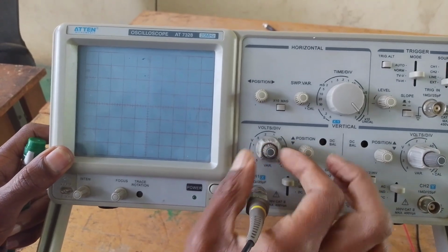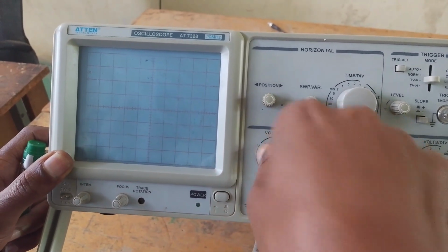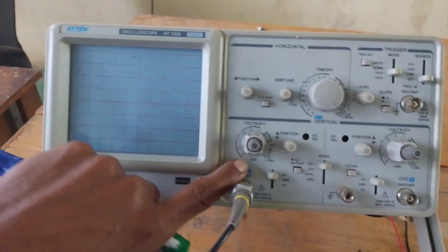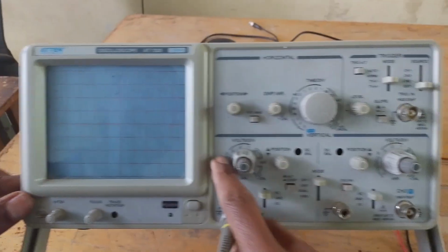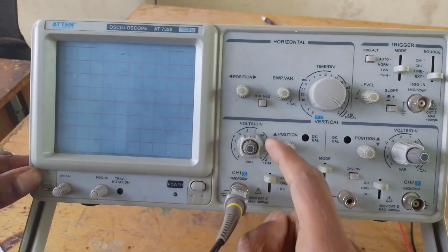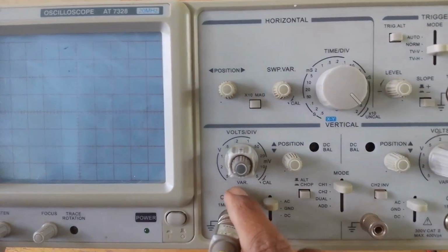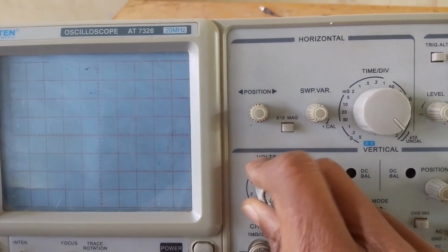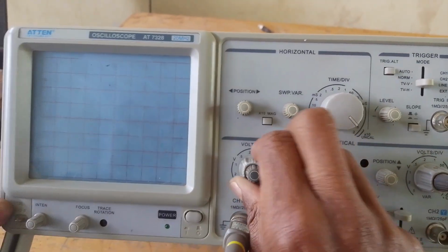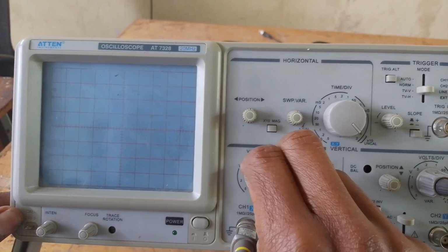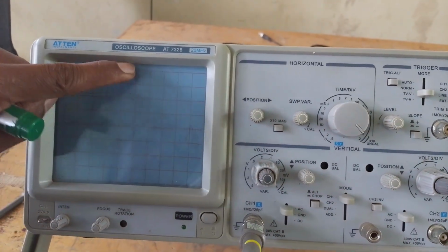So we have two setting points here. It is the smallest one. This setting must be adjusted on this one. So this is voltage, millivolts and volts. From the lower value to the maximum one, we have certain values. By using this adjustment, you can adjust any values on this one. This setting is called voltage per division, volt per division, which assigns the value of this y-axis.